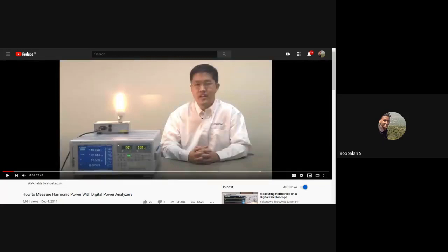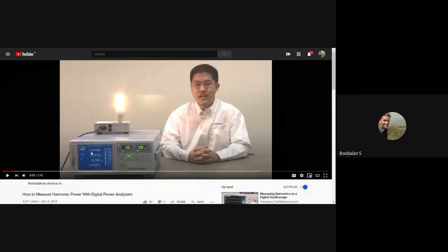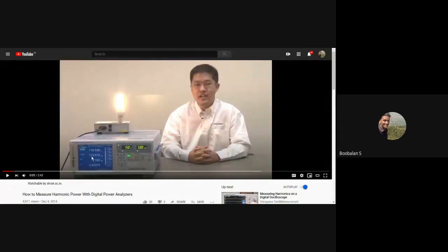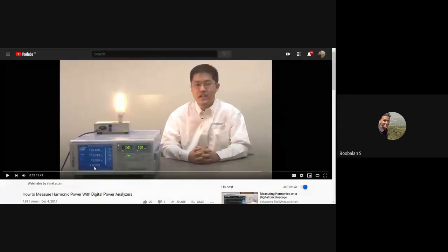Now you can see this CFL lamp which is connected, and this is my power quality analyzer, called a digital power analyzer from Yokogawa. Currently this lamp shows a voltage of about 119, that is 120 volts, and the current drawn by this lamp is about 172.614 milliampere. Total wattage of power is around 12.5 watts, and the power factor is now 0.60. So where actually the harmonics are, we'll see.